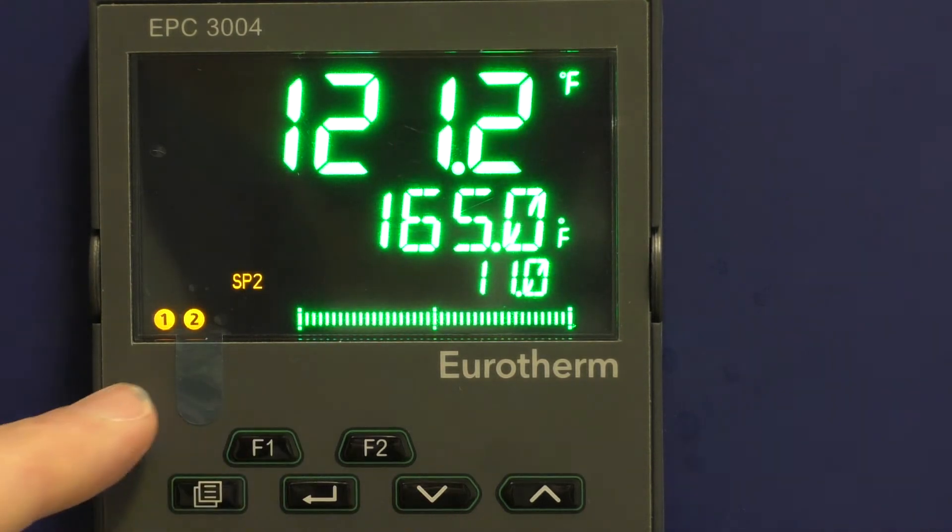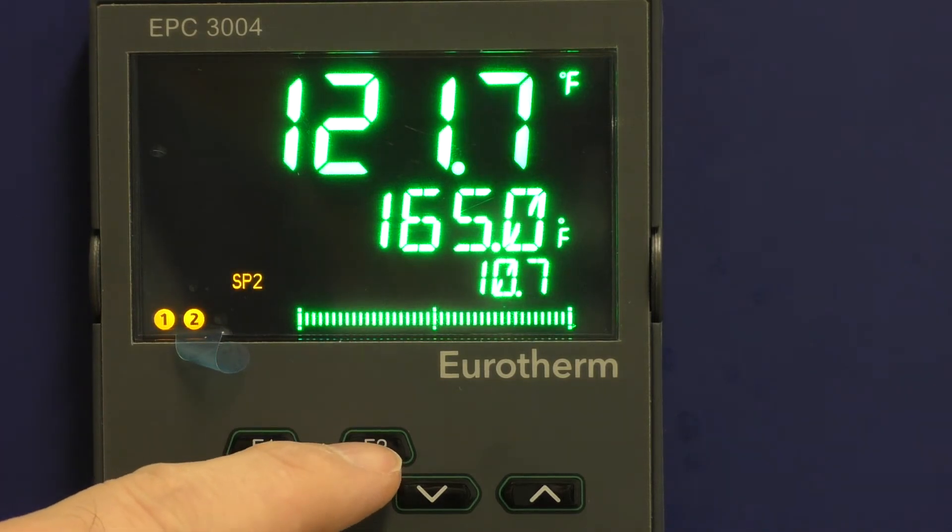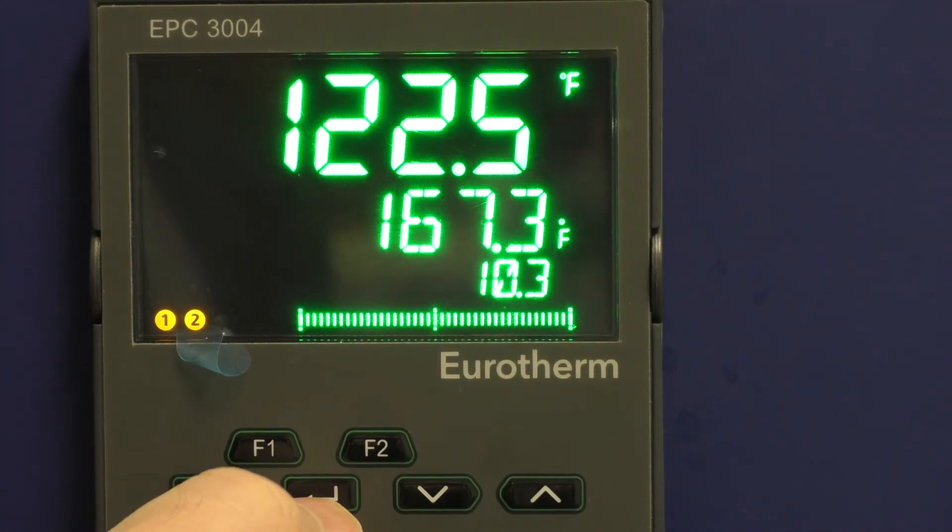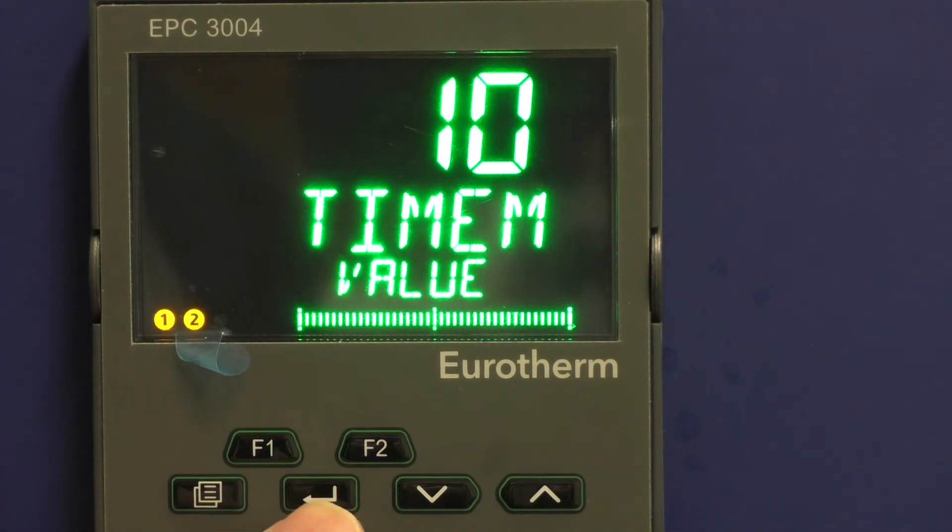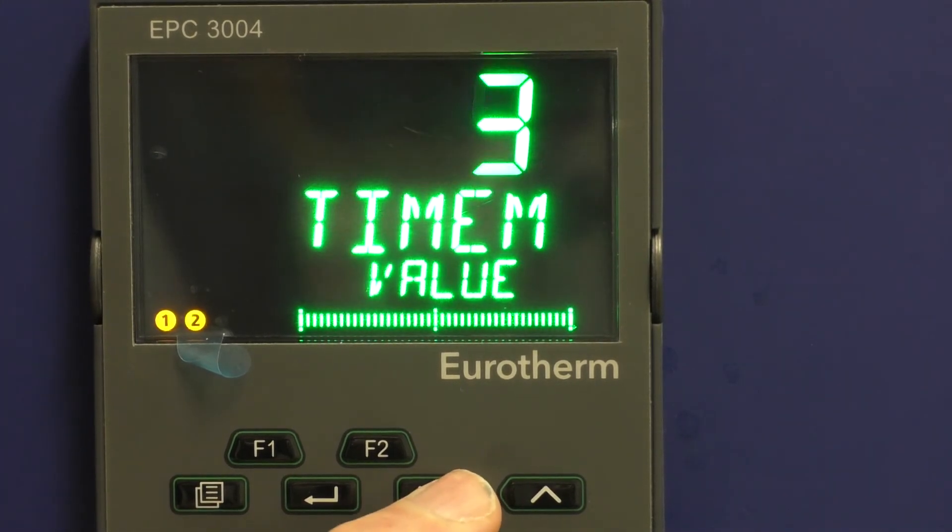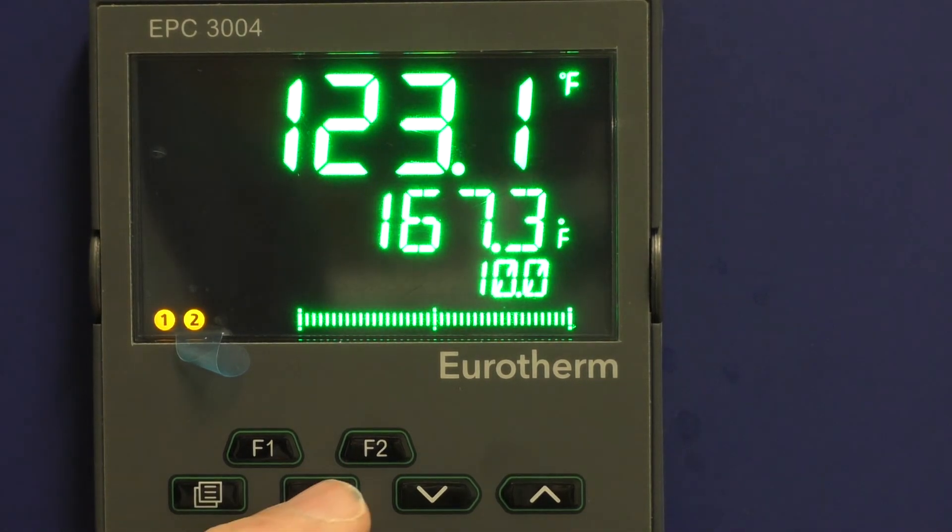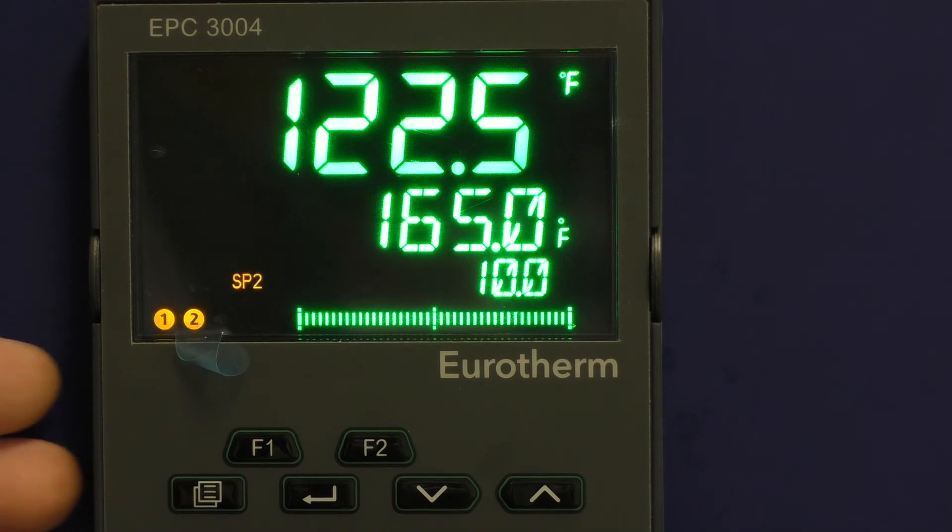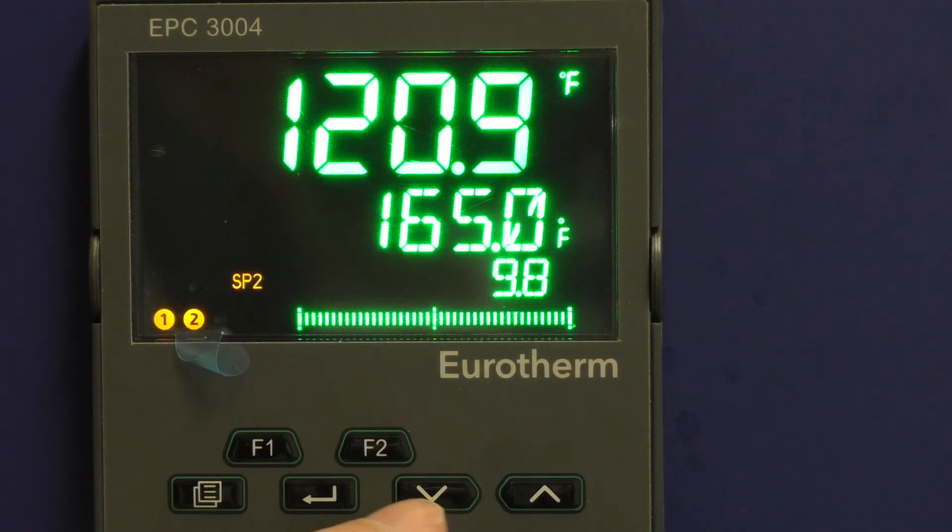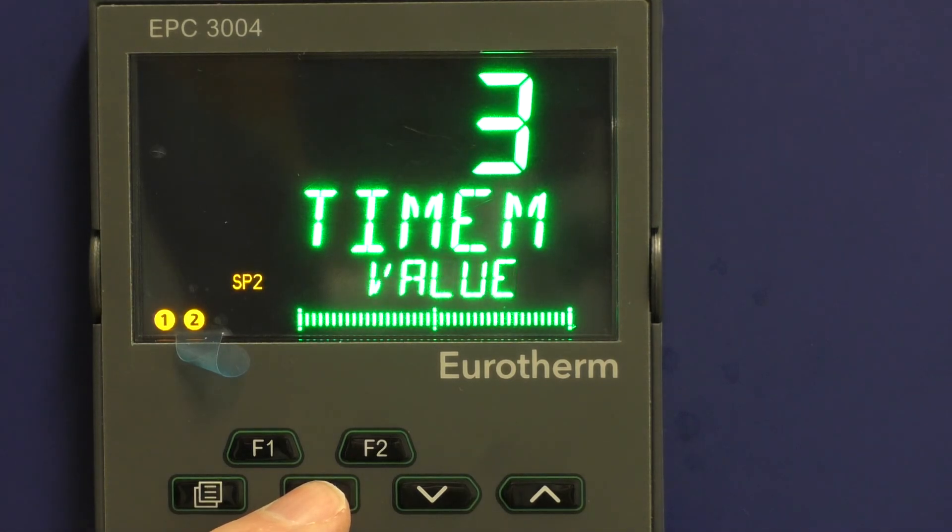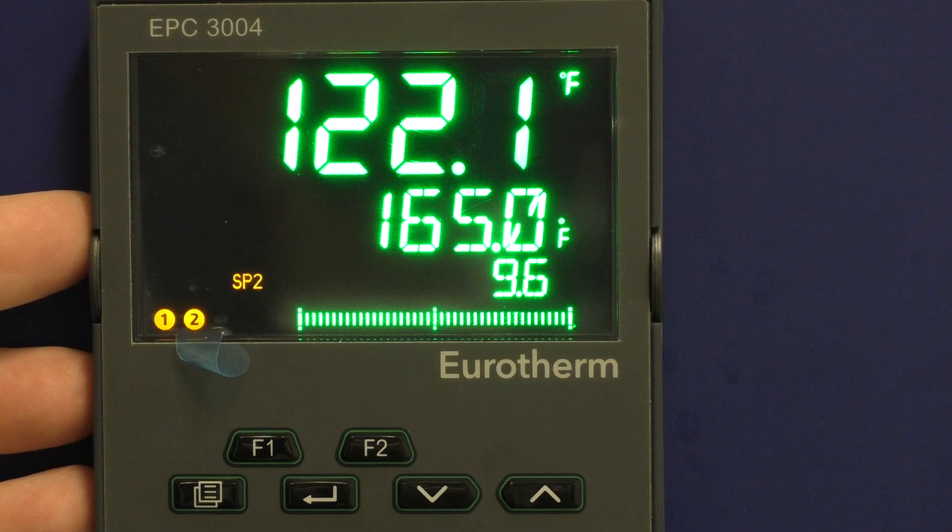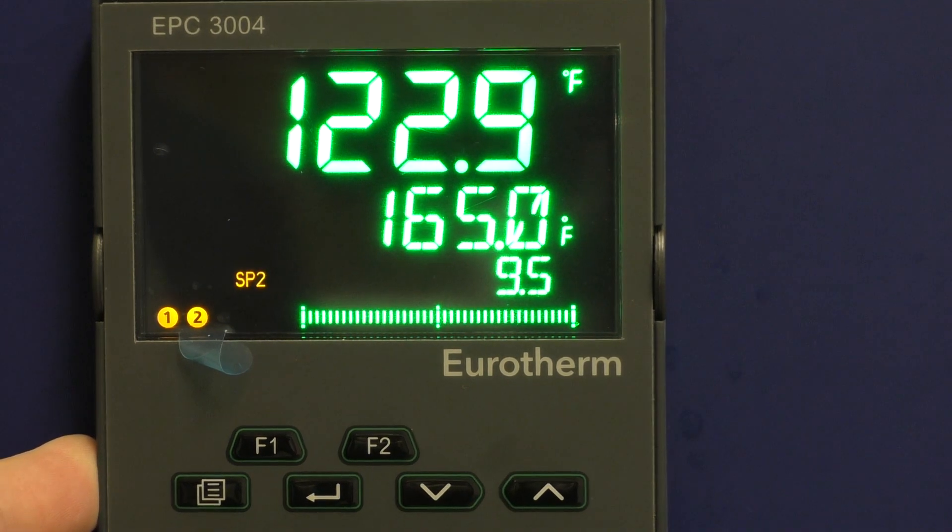Again, if you want to get out of timer mode or reset the timer, you can simply hit F2, hit the manual shut off button, because we're technically in manual mode now, and we can reset the timer to 3 minutes. Then we can go back to the home screen, we can hit F2 again, make sure the manual switch is on, and now it's going to run on that timer setting for 3 minutes. So that is the basic functionality of the new EPC-3004 controller.